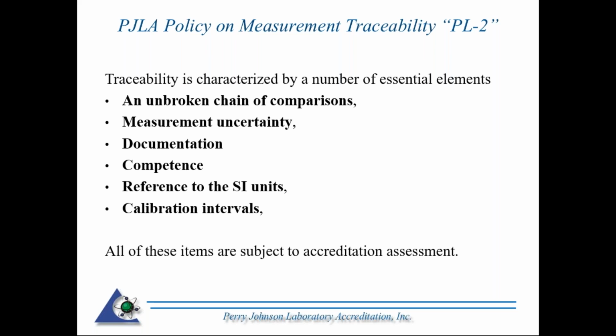Going to ensure that documentation is in order, the folks that are doing the calibration stating that the measurements are traceable, their competence, and that it's being referenced to the SI units. And that calibration is not a one-time thing, that there are calibration intervals associated with the calibrations that are being provided to the customers as far as the calibration of their standards and their reference materials. All these are subject to the accreditation assessment.